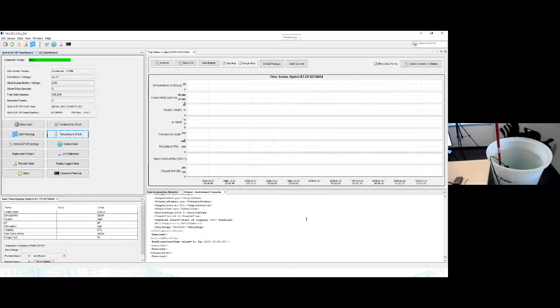Post deployment, a couple of things you're going to want to do: flush the pH module, remove the pH module, store it in the soaker block with potassium chloride solution, and then clean the externals of the instrument. We don't recommend scraping off barnacles with a metal tool, since you can damage your instrument that way.